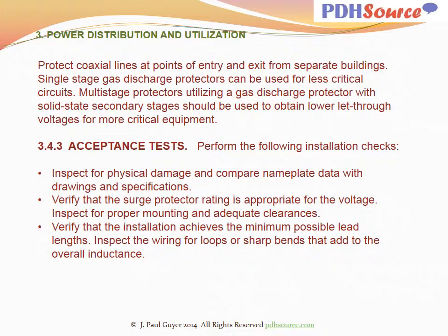Inspect for physical damage and compare nameplate data with drawings and specifications. Verify that the surge protector rating is appropriate for the voltage. Inspect for proper mounting and adequate clearances. Verify that the installation achieves the minimum possible lead lengths. Inspect the wiring for loops or sharp bends that add to the overall inductance.